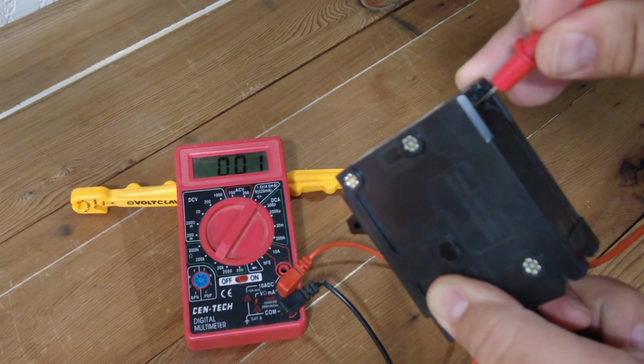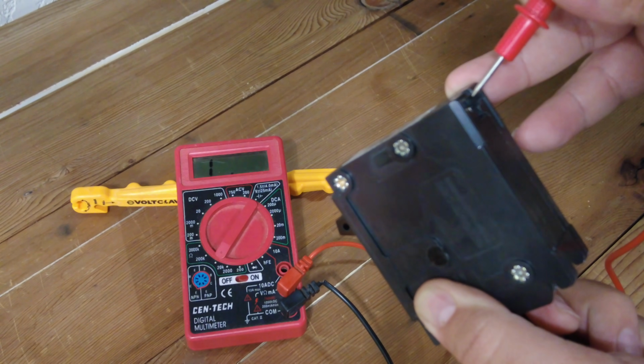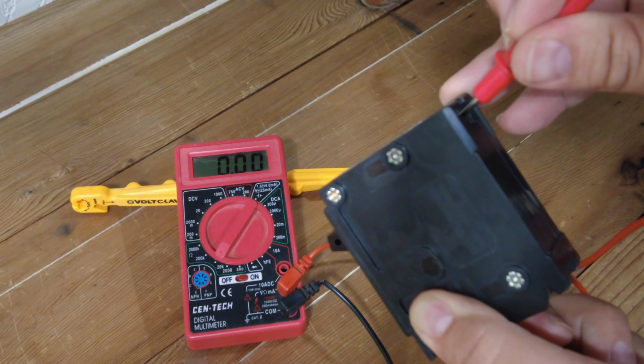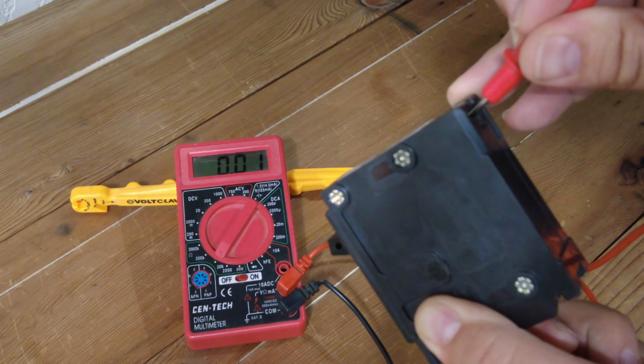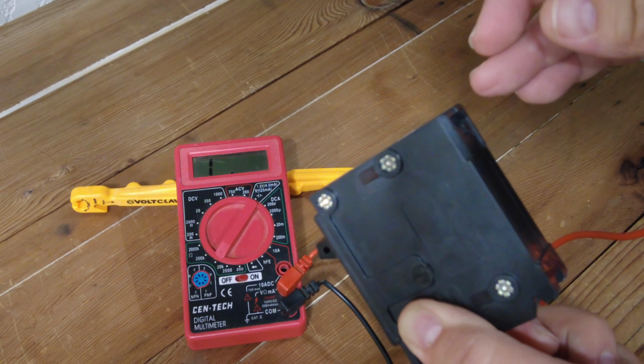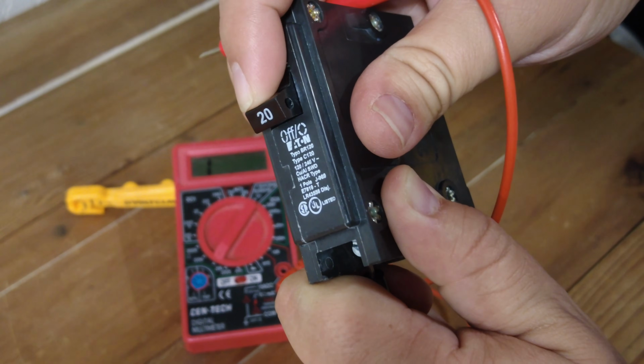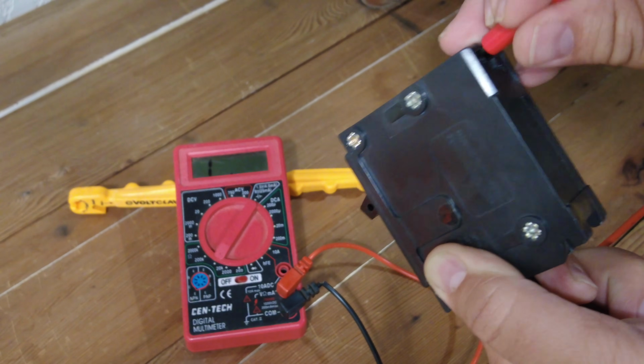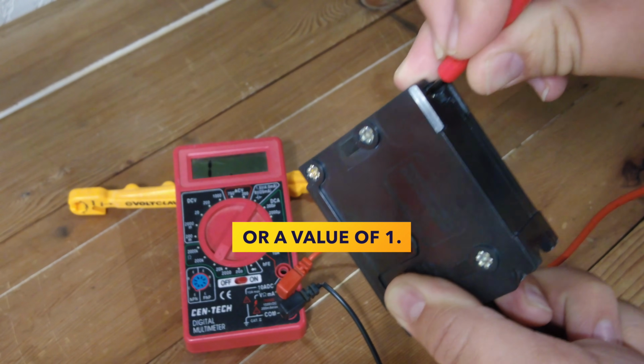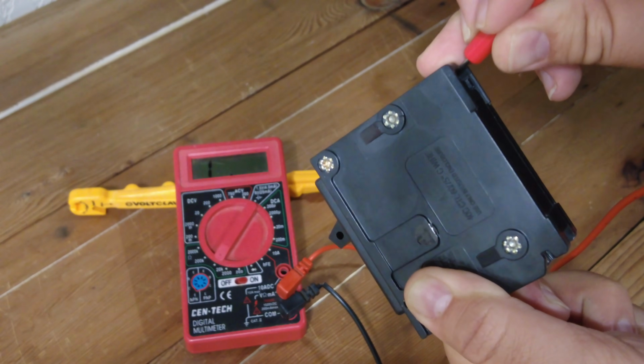With the circuit breaker in the on position, on the multimeter you should have a reading of 0 or very close to 0, and that indicates that the electricity is flowing through the breaker as it should. If it's not 0 and you see an infinity symbol or an OL sign, then that's a good indication that there's something wrong internally. Likewise, once you flip this to the off position, you should also see that infinity symbol or the OL reading to indicate that there's no electricity or no circuit that's completed inside of this. And if you have anything other than that, then it needs to be replaced.